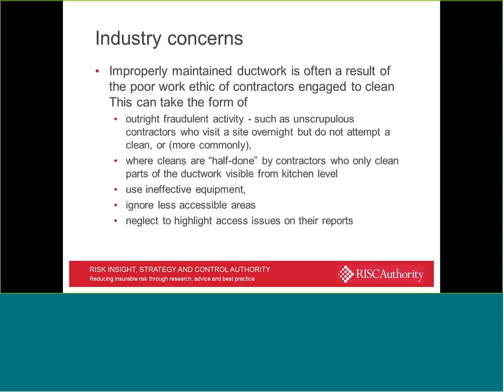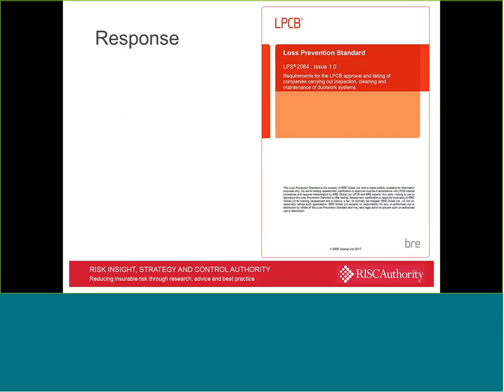This is not hearsay. This is not something that's been imagined. This is as a result of research that's been undertaken, and clearly quite shocking. Bearing in mind that the trade association at the time, HVCA or BESA at the time, had a certification scheme of sorts, but clearly it was suggested that certification scheme maybe wasn't as fit for purpose as it should have been. The response to that was an approach to Loss Prevention Certification Board to develop a certification standard for contractors involved in cleaning and maintenance of ductwork systems.